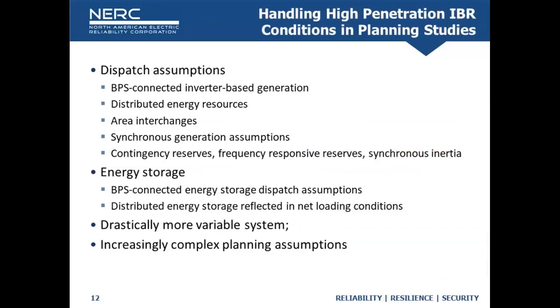How do I create a case that's predominantly inverter-based resources, specifically when I've got a whole bunch of distributed energy resources out there as well? How do I set my area interchanges? What do I set my generating assumptions at? How do I make sure I'm carrying a sufficient amount of contingency reserve, frequency response reserve? How much synchronous inertia do I have in our system? That's requiring a lot more coordination with neighboring transmission planners, planning coordinators than has ever been done in the past. So we've got a lot of work to do to make sure that the cases are of high quality and they're actually going to be useful in identifying reliability issues.